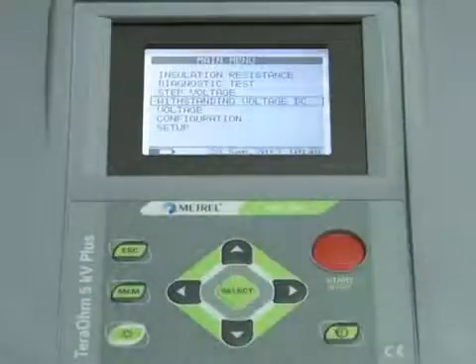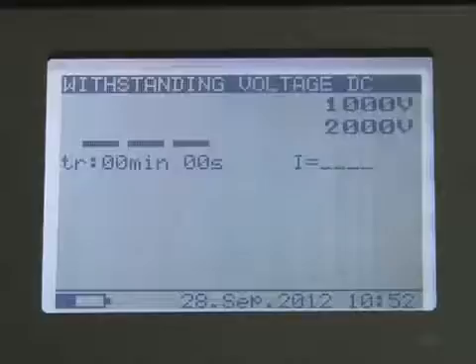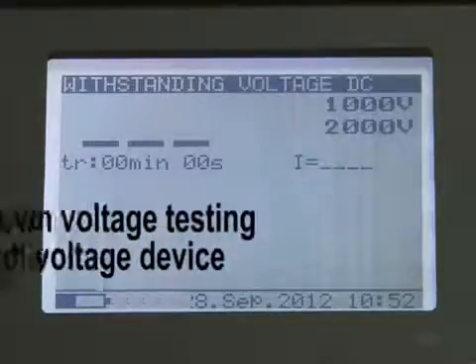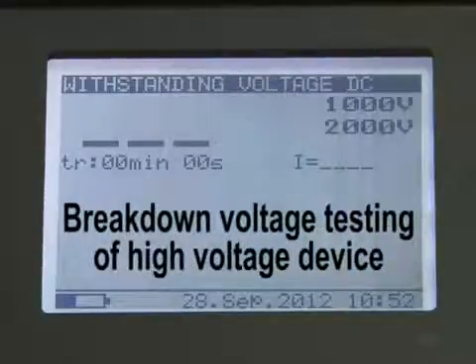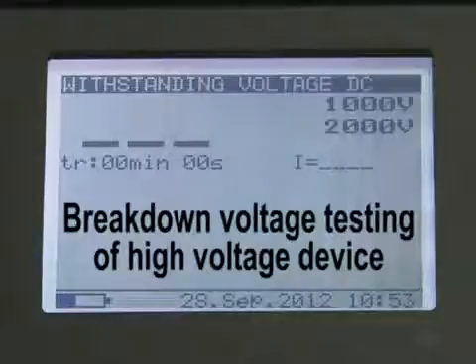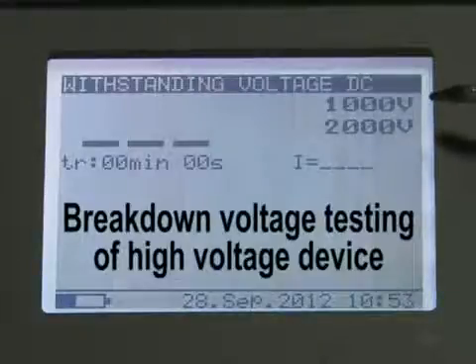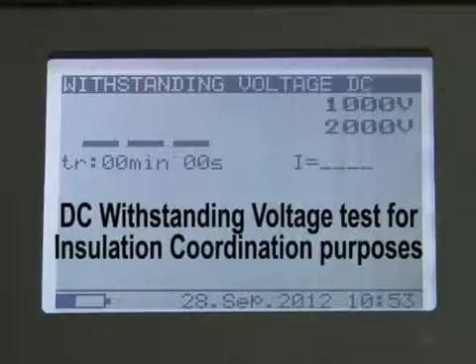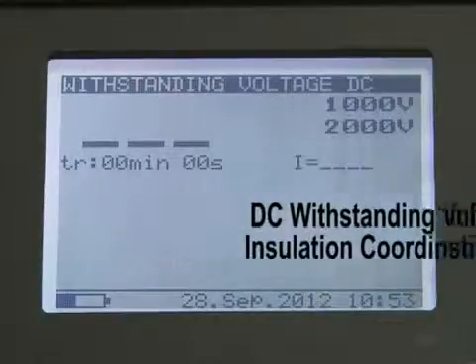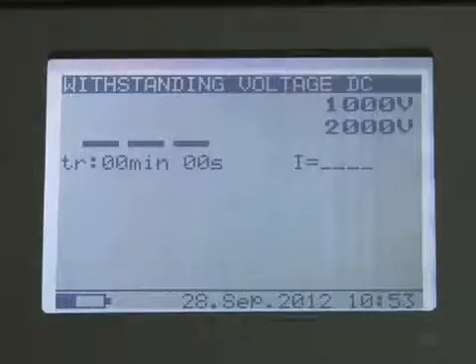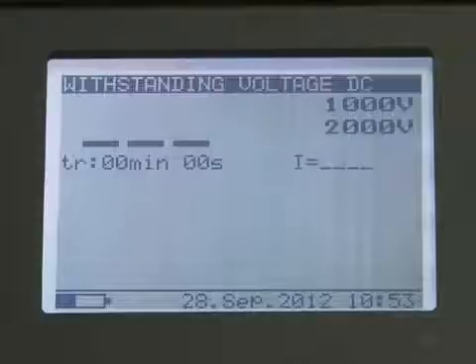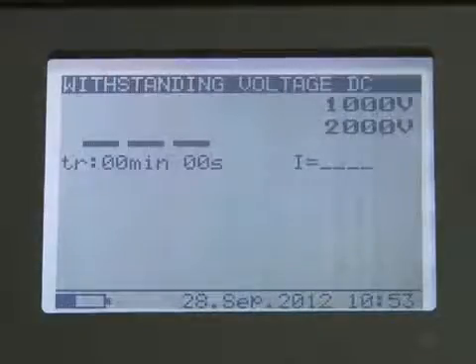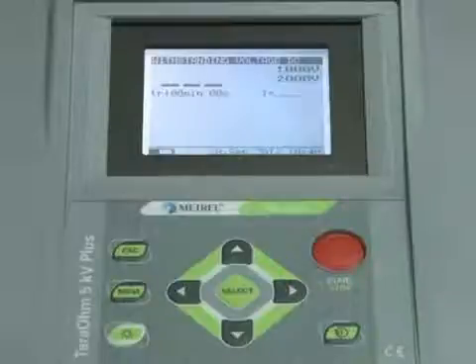The instrument offers two types of tests: breakdown voltage testing of high voltage devices such as transient suppressors, and DC withstanding voltage test for insulation coordination purposes. Both functions require breakdown current detection. The test voltage is increased from the starting voltage to the stop voltage over a predefined time.